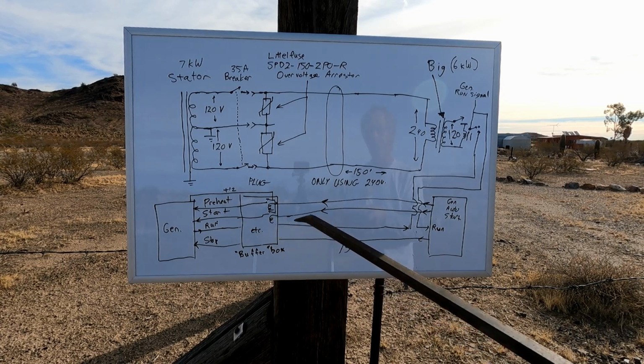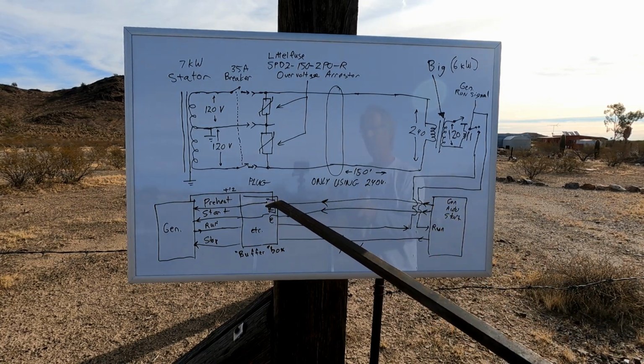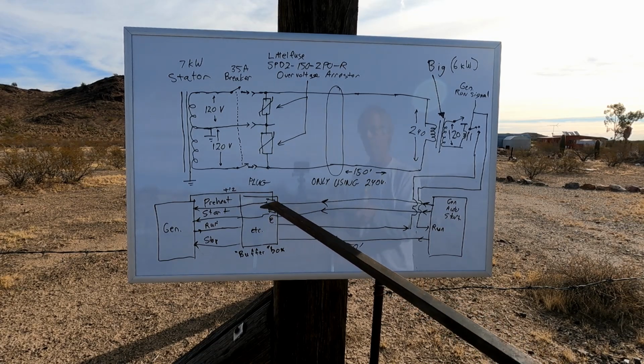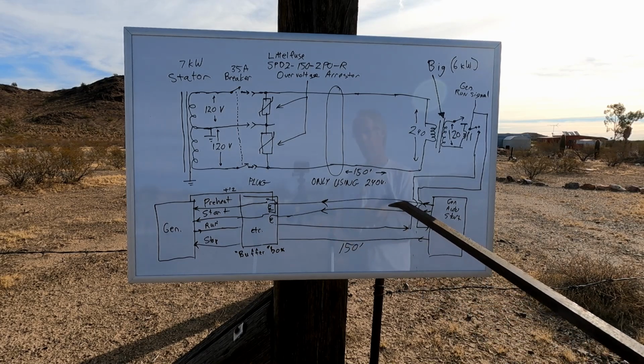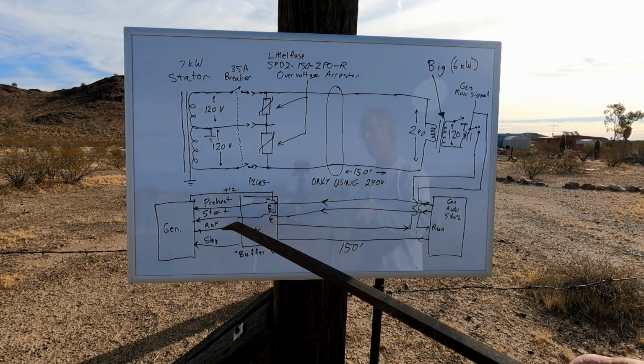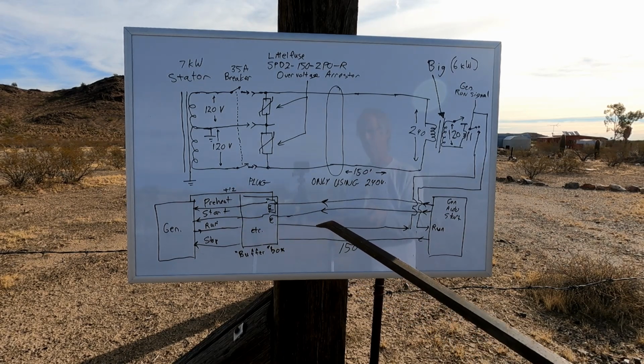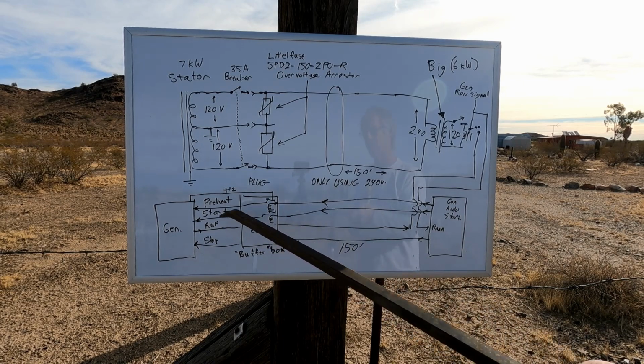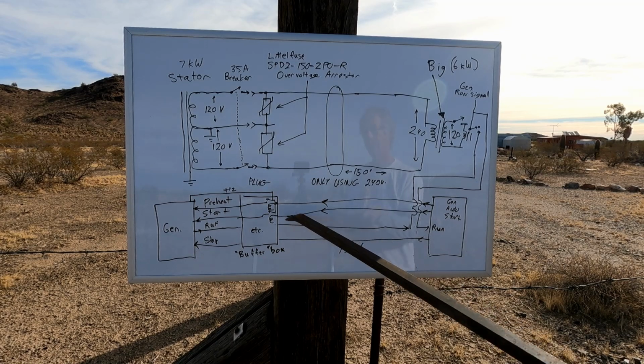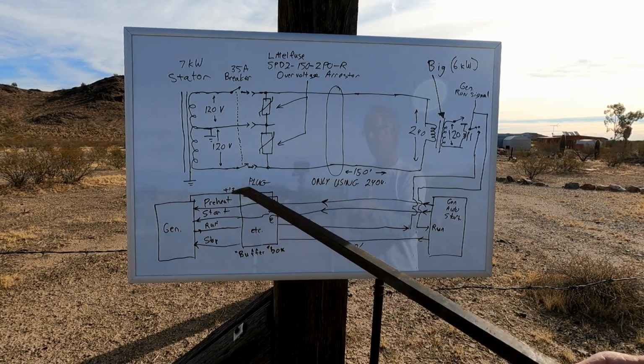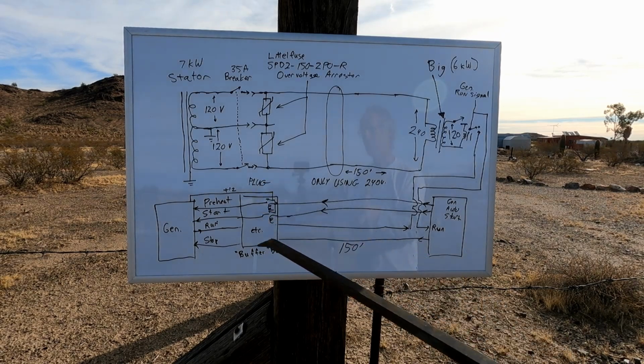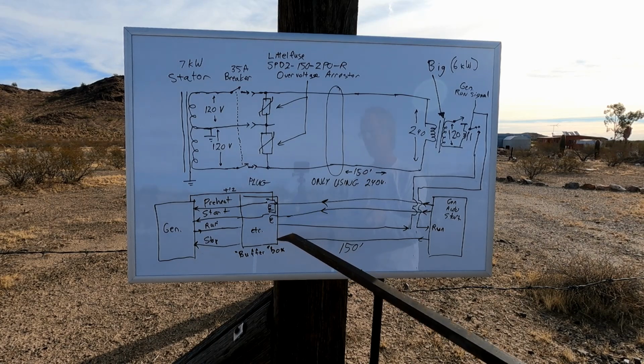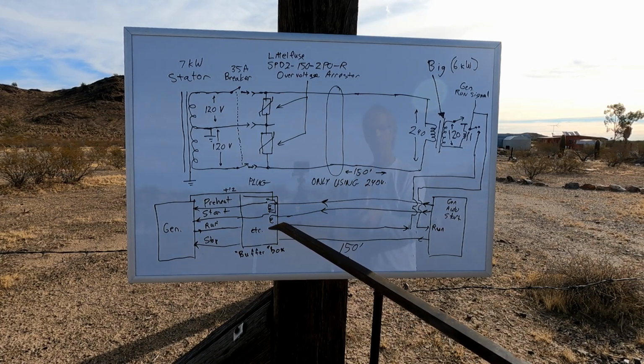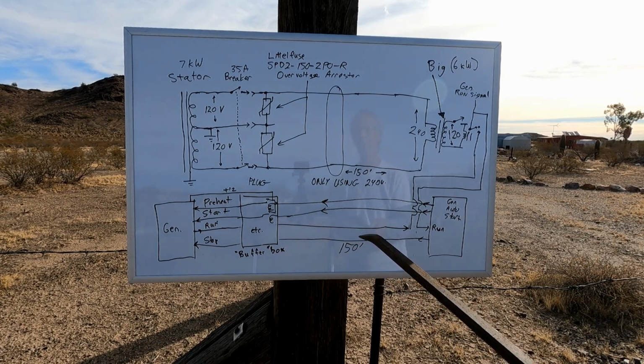And I'm indicating here my little buffer box and how each one of these control lines at the far end by the generator only activates a relay. Its signal really goes no further, because with the 150 foot feed, when I tried to tie these signals directly into these preheat, start and run nodes within the generator, I had really odd behavior, which I had to attribute to there being actually too much current in these lines, over 150 feet on a small cable. So I built my little buffer box, which basically puts a relay in between every one of these lines. I'll include information on Kubota generators because there's at least one supplier of Kubota generators that actually adds a module inside the generator that greatly simplifies the installation of auto start over what I've done here. But this is what I did in my time. So that's the system looking at the generator electrically.